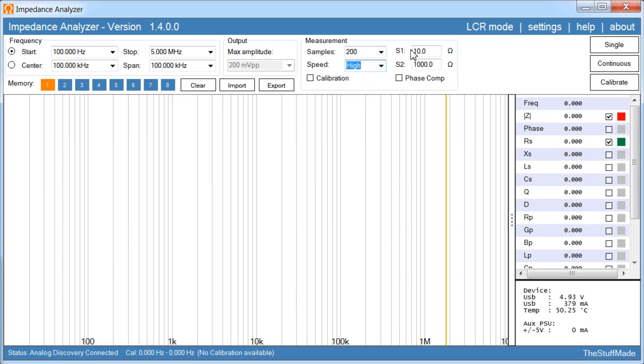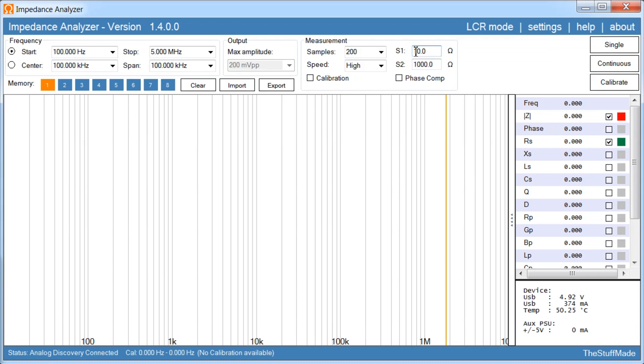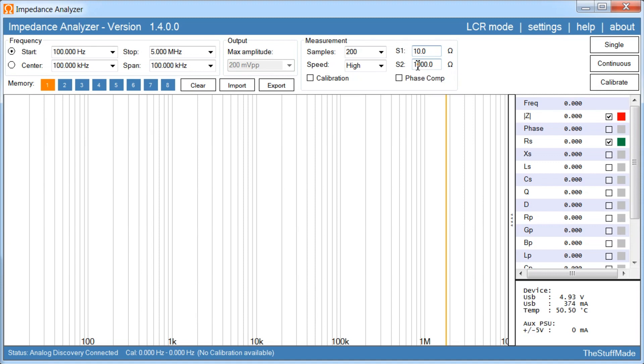Then we have two settings over here, S1 and S2. The top one decides when we are going to switch between the smallest shunt resistor and the medium shunt resistor, and the second one when we are going to go from the medium shunt resistor to the highest value shunt resistor. If you are having trouble getting a good measurement, it will often help to adjust these settings here.